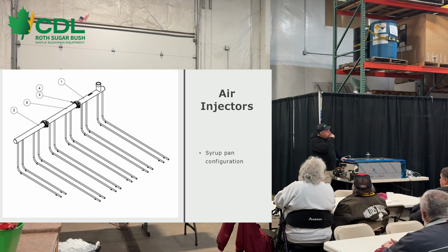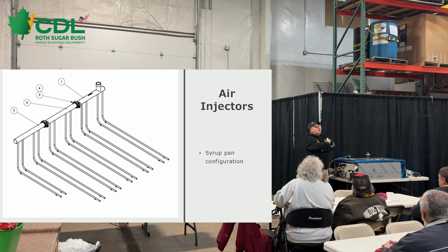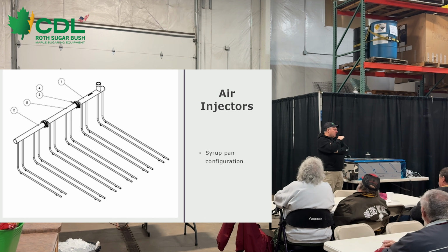If you have air injectors, do you always have to run them, or is it bad if you have them and you're not running them while you're boiling? Yeah, so if they're in your evaporator and you're not running them, a layer of niter will build up over the holes in the air injector. They're very, very small, fine holes, and if you're not running air through them, they'll niter up right away.